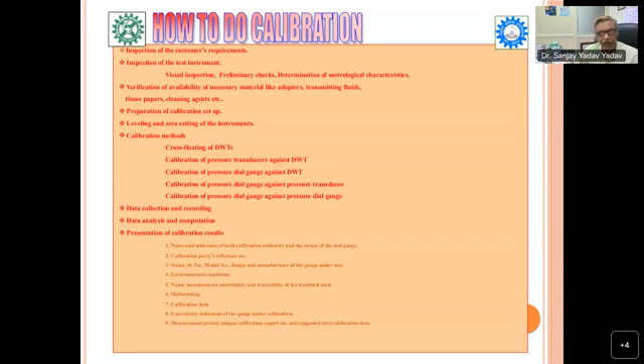So please remember, I have seen a few people calibrating a dead weight tester against a dial gauge. So this is very, very important. Your reference equipment must be of higher accuracy. Data collection and recording, then data analysis and computation, and finally presentation of calibration result is another important step.